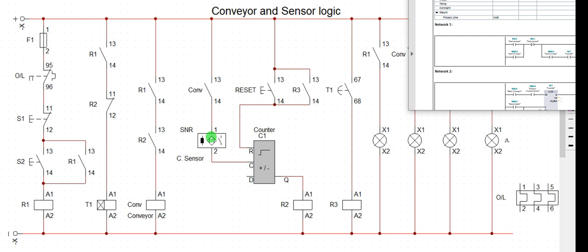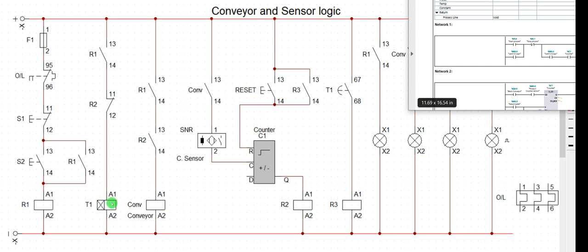The counter logic is responsible for counting. This is the sensor that counts the number of items passing and registers the count here. When the count is completed, this relay here gets activated to shut down the conveyor. Once it shuts down, the same relay will also energize a timer — remember that in network two, when the counter network gets deactivated, two things happen: the conveyor is deactivated and a timer is activated. Similarly here, when this output is disabled, the conveyor is deactivated and the timer is activated.